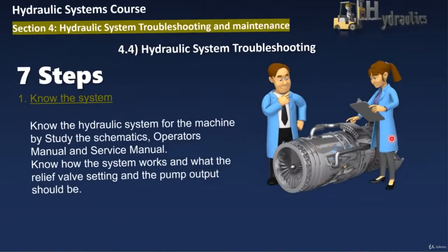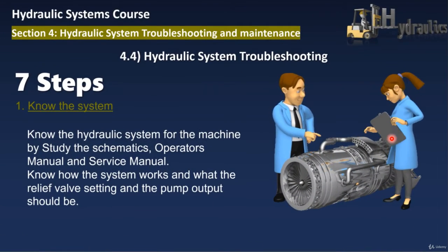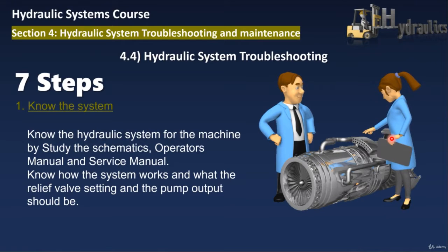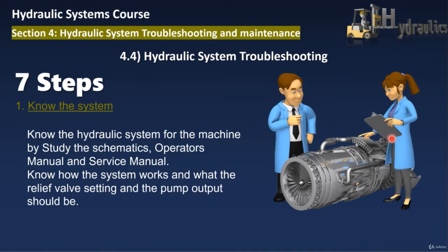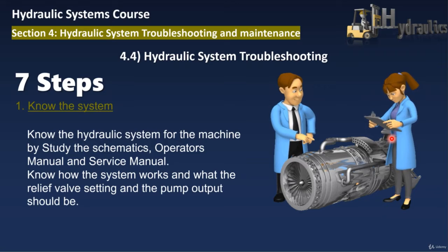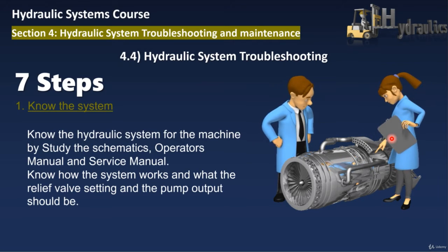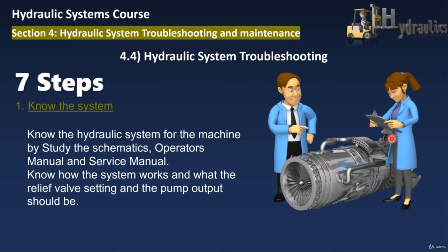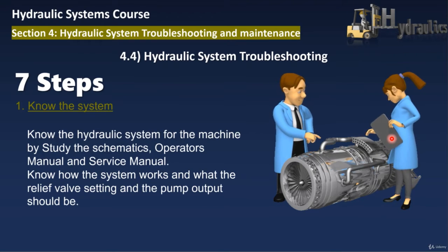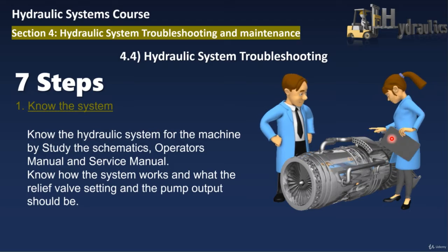So let's start with the first step, which is know the system. You have to know the hydraulic system for the machine by studying the schematics, operation and service manuals. You also have to understand how the system works and what the relief valve setting and the pump output should be.